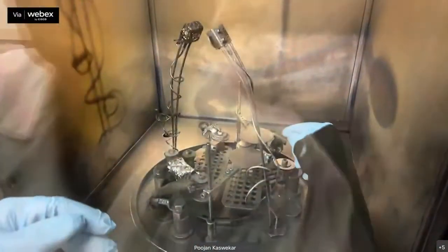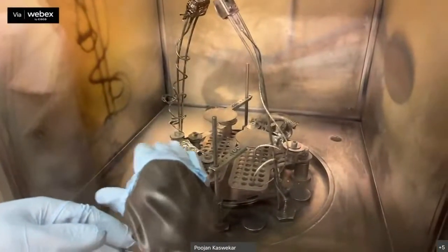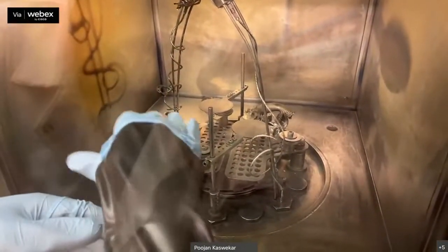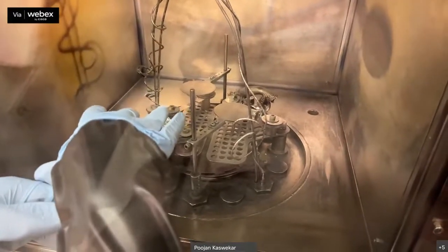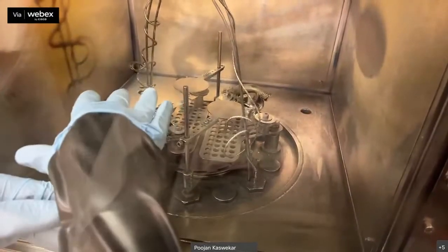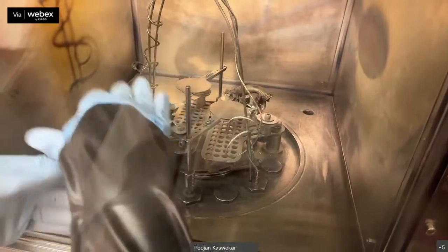You can see the shutters here. This is shutter 1 and this is shutter 2. Close shutter 2. There is a shutter on top of silver so there is no unusual deposition of silver. If in the middle of the process you don't want to deposit any silver, you can close the shutter on top of the silver so it won't evaporate.